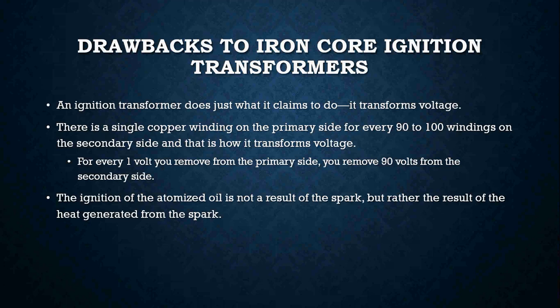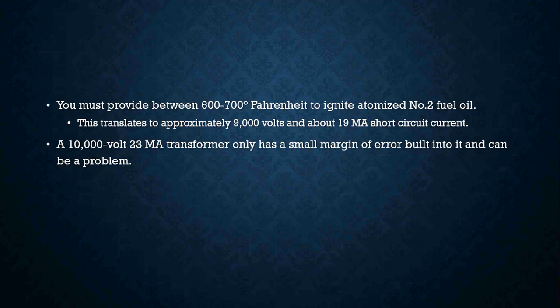So if I do not have enough voltage coming out of my secondary side, I'm not going to have the correct amount of heat needed to properly atomize and ignite that oil, because I'm losing the voltage. So you must be able to generate at least 600 to 700 degrees from that spark to ignite number 2 fuel oil. That translates to approximately 9,000 volts and about 19 milliamps of short circuit current. Now, most ignition transformers are set up for 10,000 volts with 23 milliamps of current. That provides a small margin of error, but obviously if we start having voltage issues, that can start to create a problem.